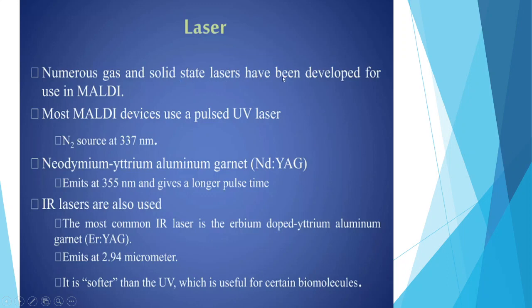Numerous gas and solid-state lasers have been developed for use in MALDI. Most MALDI devices use a pulsed UV laser nitrogen source at 337 nanometers. Neodymium-yttrium aluminum garnet (Nd:YAG) emits at 355 nanometers and gives a longer pulse time. IR lasers are also used; the most common IR laser is the erbium-doped yttrium aluminum garnet (Er:YAG), which emits at 2.94 micrometers. It is softer than UV lasers, which is useful for certain biomolecules.